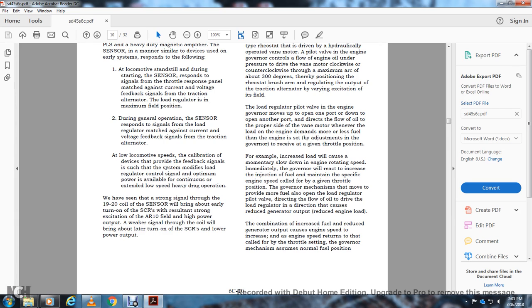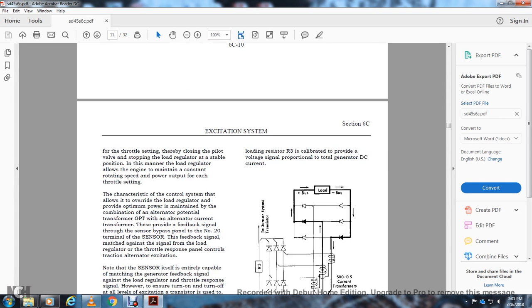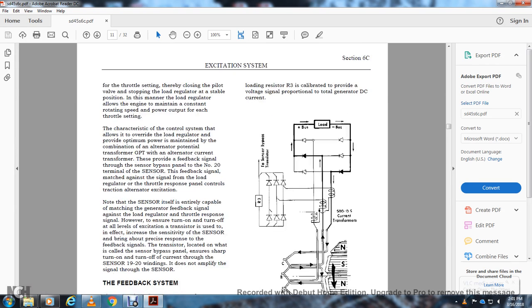The combination of increased fuel and reduced generator output causes the engine speed to increase, and as the engine speed returns to that called for by the throttle setting, the governor mechanism will assume the normal fuel position for the throttle setting, thereby closing the pilot valve and stopping the load regulator at a stable position. In this manner, the load regulator allows the engine to maintain a constant rotating speed and power output for each throttle setting.